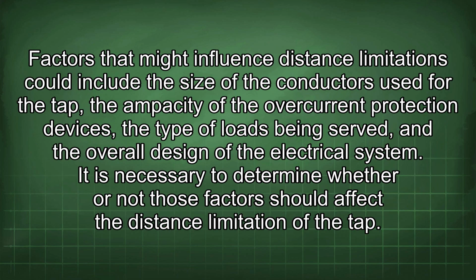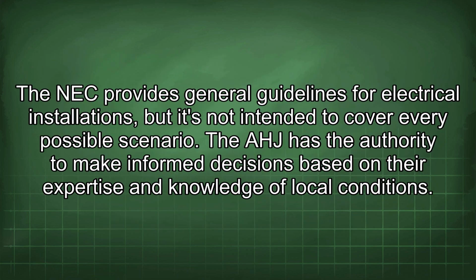Factors that might influence distance limitations could include the size of the conductors used for the tap, the ampacity of the overcurrent protection devices, the type of loads being served, and the overall design of the electrical system. It is necessary to determine whether or not those factors should affect the distance limitation of the tap. The NEC provides general guidelines for electrical installations, but it's not intended to cover every possible scenario. The AHJ has the authority to make informed decisions based on their expertise and knowledge of local conditions.